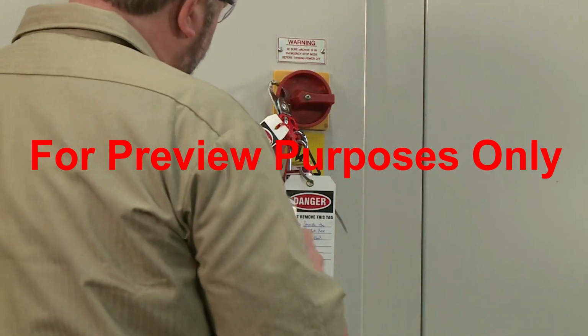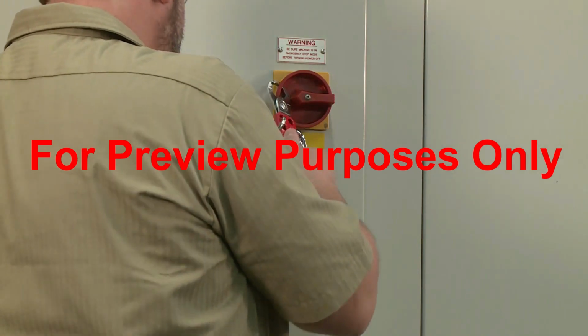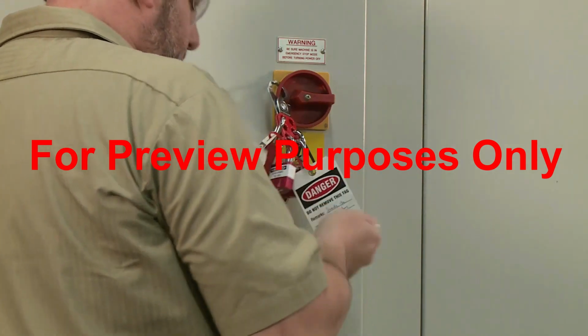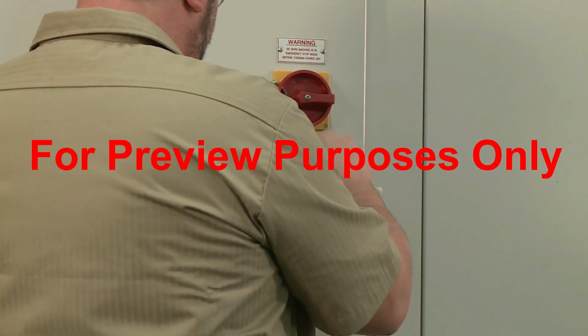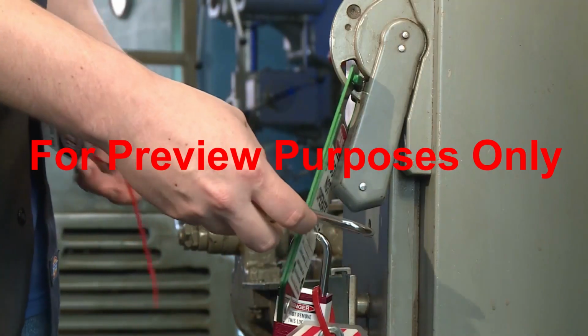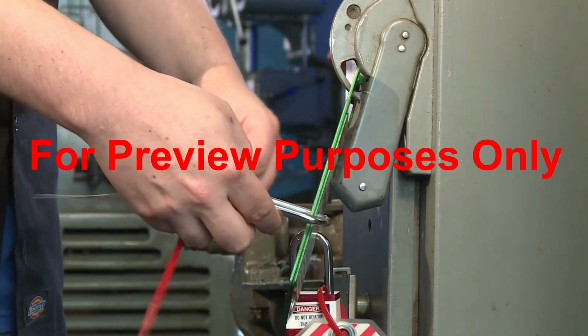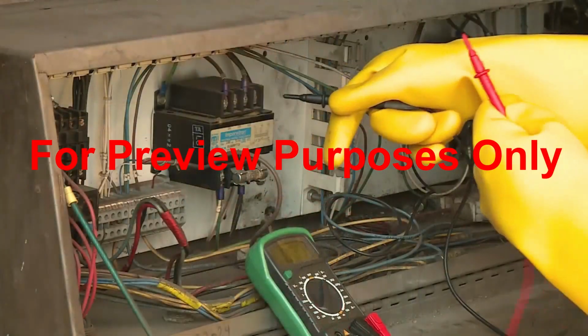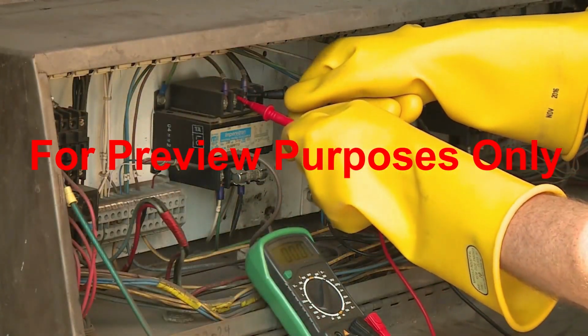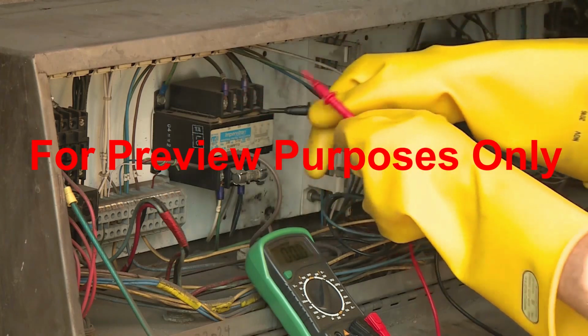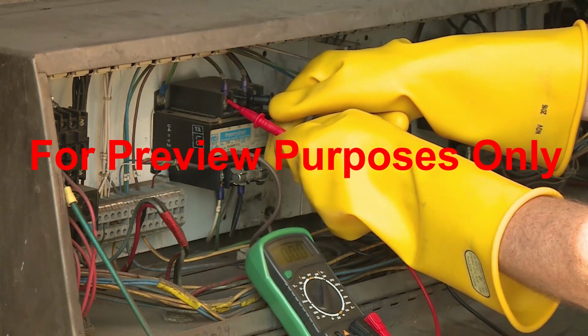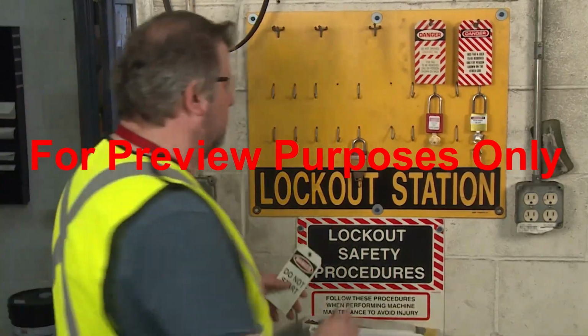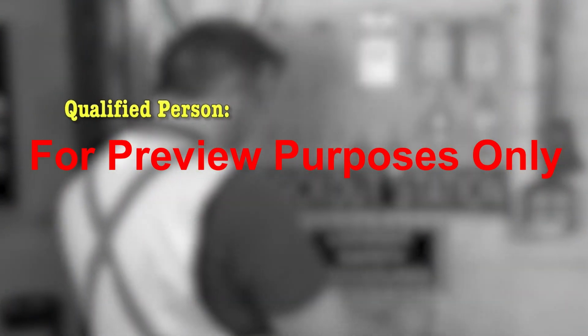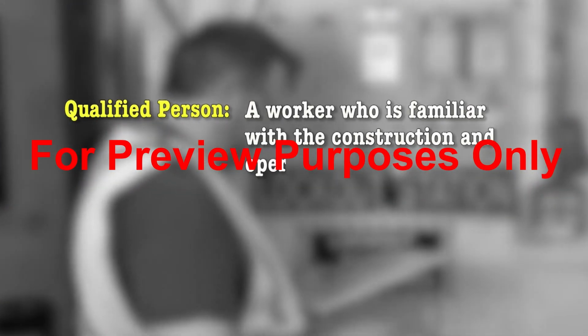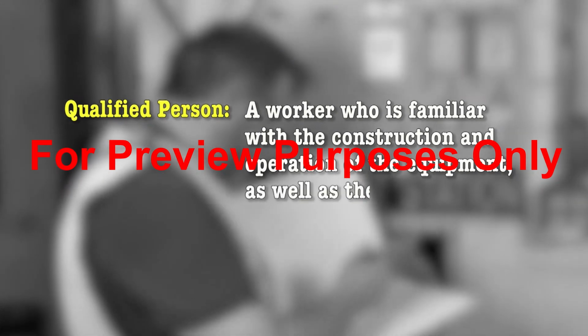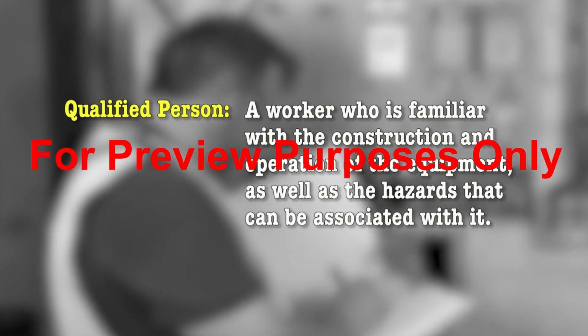In some situations, several people can be involved in locking out power sources. In these cases, each of them should apply their own locks. Special lockout devices are made that allow multiple locks to be attached to a single switch. The equipment that is being worked on and its electrical circuitry should then be tested by a qualified person to verify that the power is truly off. OSHA defines a qualified person as a worker who is familiar with the construction and operation of the equipment, as well as the hazards that can be associated with it.